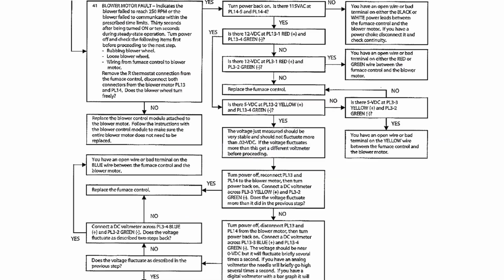Some manufacturers will have flow charts doing the same thing, the fault code 41 blower motor fault, and then they will walk you through the various wires and what DC voltage you should see as far as communication control.